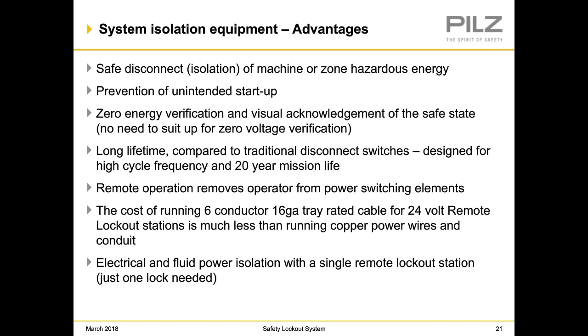So some advantages of system isolation equipment. Safe disconnect isolation of machine or zone hazardous energy. The prevention of unintended startup, because if power is lost and the power comes back on, a start signal would be needed to allow power to return to the machine, since, again, the contactors would be open until a start signal is given. Zero energy verification and visual acknowledgement of the safe state, so there's no need to suit up in arc flash gear for zero voltage verification.